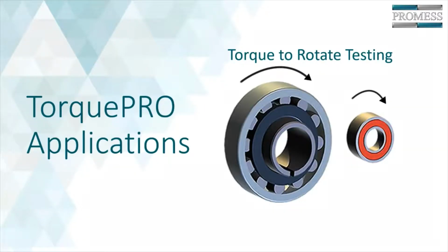Another very common application for the Torque Pro is torque to turn or torque to rotate testing. Torque to turn testing consists of rotating an assembly or component a defined amount while monitoring the peak and average torque developed while completing commanded rotation. Some examples of torque to turn or rotate testing are bearings. Rotating bearings or assemblies utilizing bearing interfaces to determine that the torque to turn them is within specification. This allows defective components or alignment and tolerance issues to be detected before the part leaves the station.